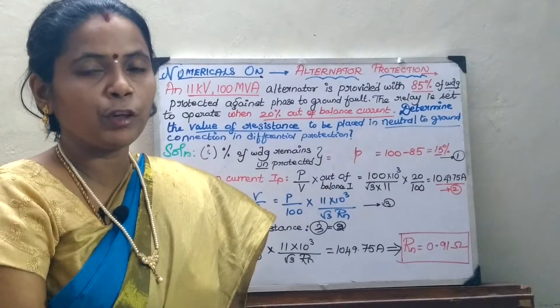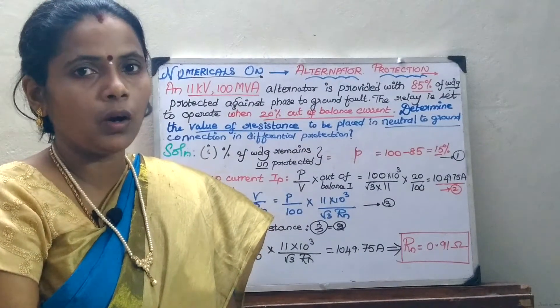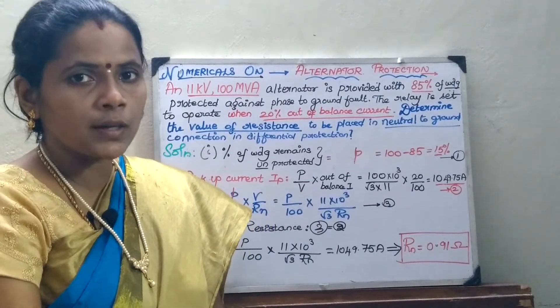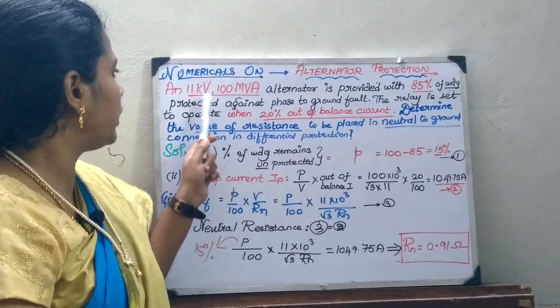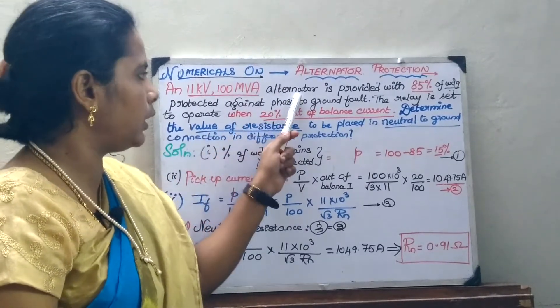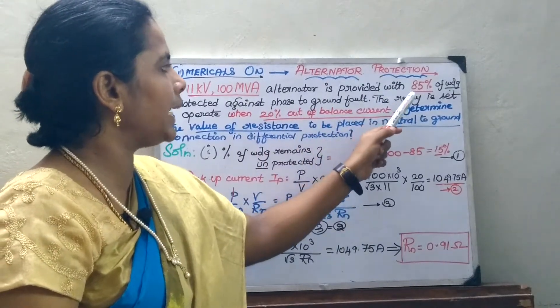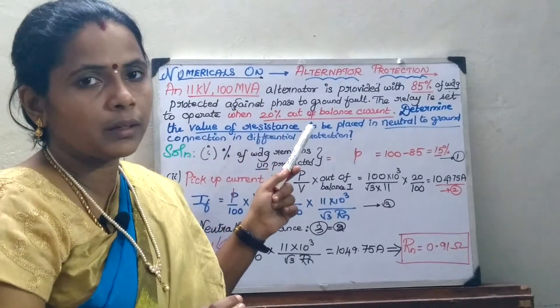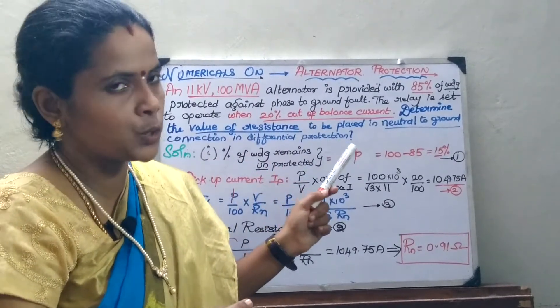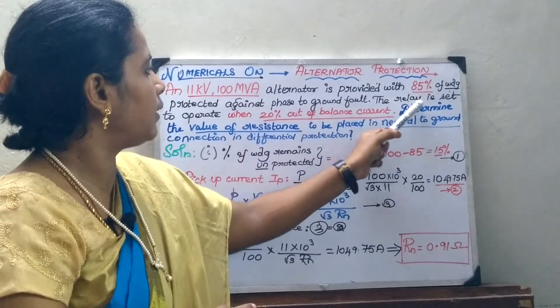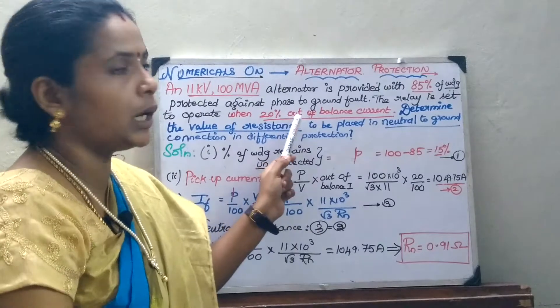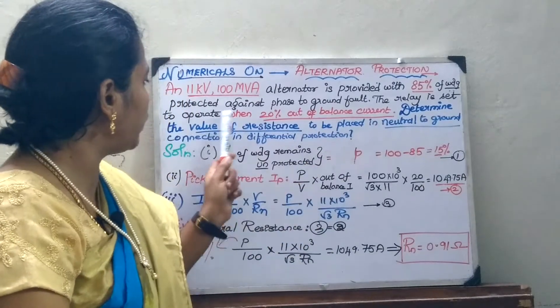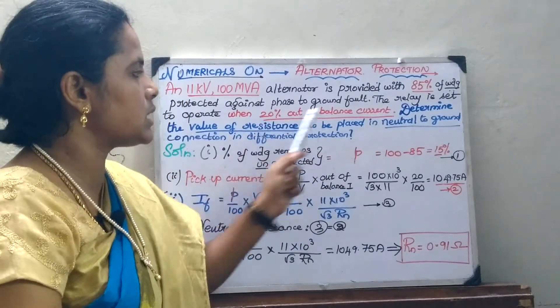In today's session, we will be seeing a numerical on alternator protection. Here we have chosen an 11 kV, 100 MVA alternator where 85 percentage of the winding is protected. The relay is set to operate when there is a 20 percentage out-of-balance current. We are asked to find out the value of the resistance in the neutral connection.